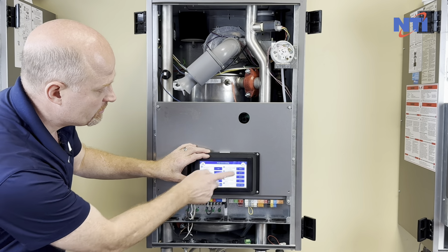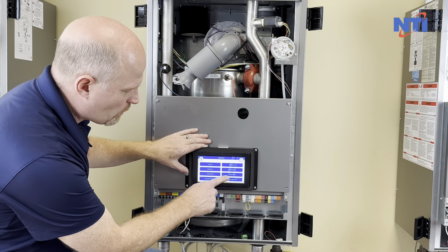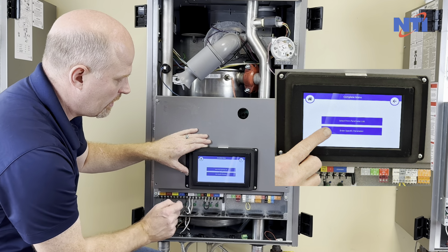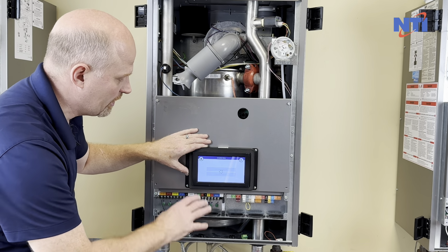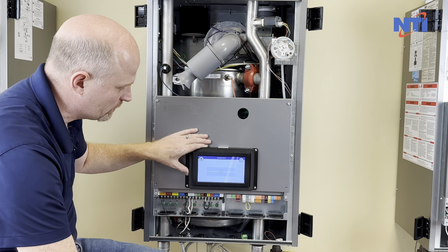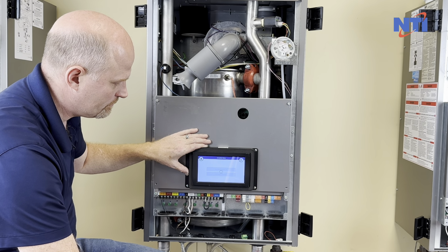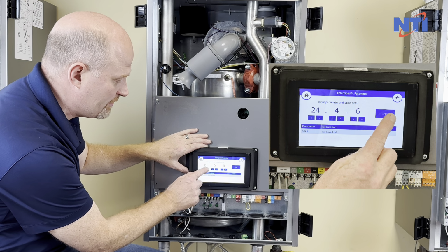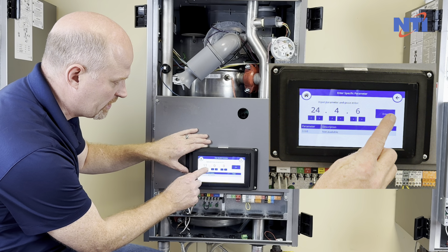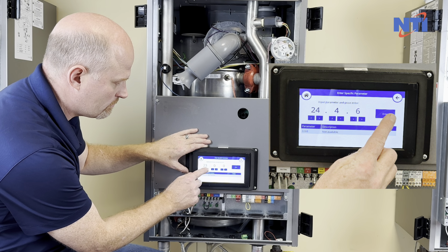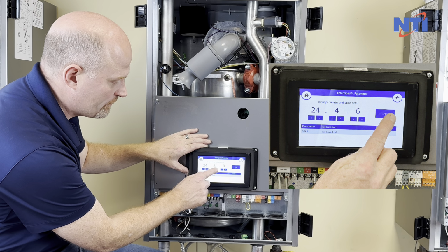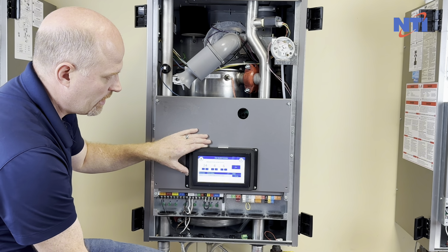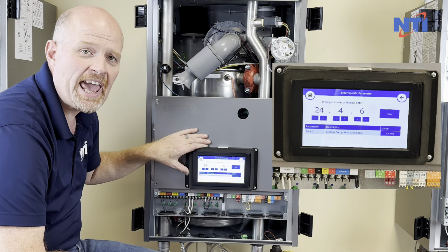Now that we know how to set the pumps, let's look at fine-tuning them. Now we're going to select Complete Menu. We're going to enter a specific parameter, and this takes a minute to load because the controller screen has to bring all the settings up into its memory. Now that that's complete, we're going to go to menu 24. So you keep tapping this till you get to 24.4.6. And this lets you set the system pump activation logic.